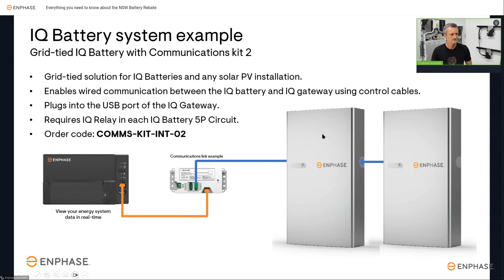It enables communication between the IQ battery and the IQ gateway using the control cable system of the battery, converting to a small USB connection back to the IQ gateway itself. For any IQ battery circuit you install, as a point of note, you will use an IQ relay as well - a grid protection device. Without the system controller, you'll need one IQ relay on each IQ battery circuit in a grid-tied scenario.